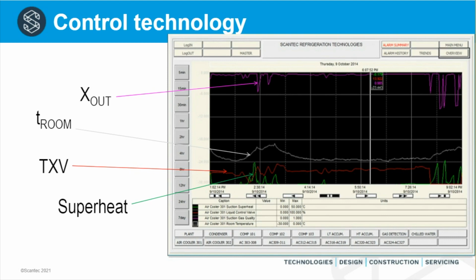You can also see that the room temperature is quite steady, and you can also see that the expansion valve position, this is the one that is titled TXV, more or less in the middle of the picture to the left. The TXV position, or the expansion valve position, does respond to wet suction. So when X out indicates wet suction, the expansion valve closes. If this expansion valve was to control in response to the superheat signal, it is highly likely that the operation would be far more erratic and hunt far more. So the lesson or the takeaway out of this is that using quality control will deliver a more stable control than superheat-based control.